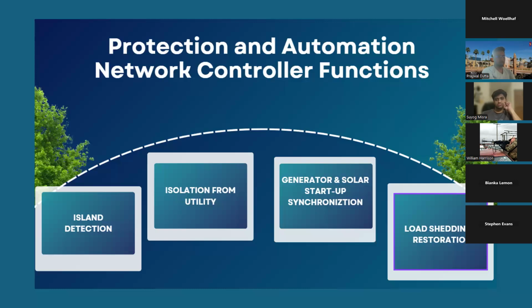Restoration and synchronization to utility. When a utility source returns, the system monitors it for stability. Once verified, the controller performs a closed transition resynchronization to grid standards and reconnects loads and phases. So in summary, this networked microgrid with solar and backup generation relies on well-coordinated protection and automation strategies managed through a cell architecture. These layers ensure fast islanding, safe isolation, controlled restoration, and flexible load management, all crucial for resilient and sustainable power delivery.